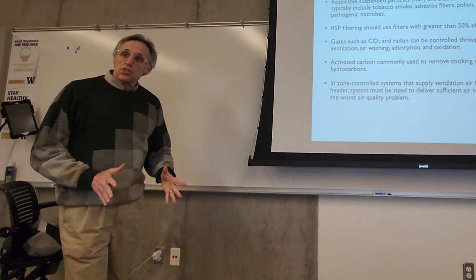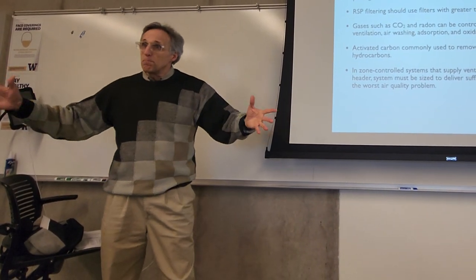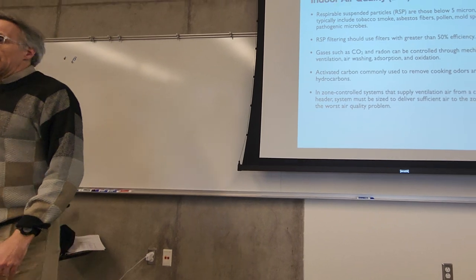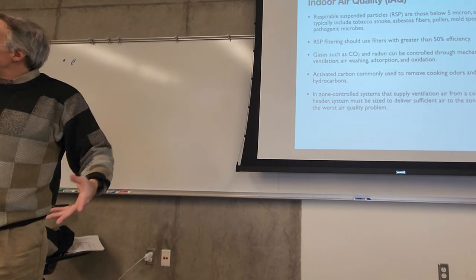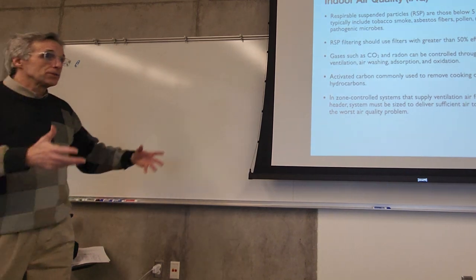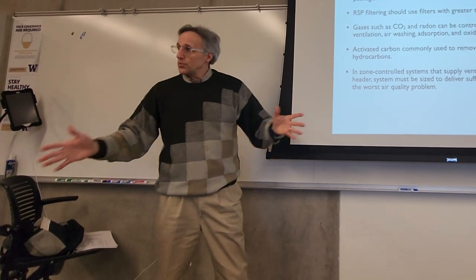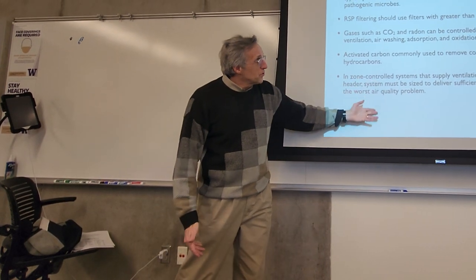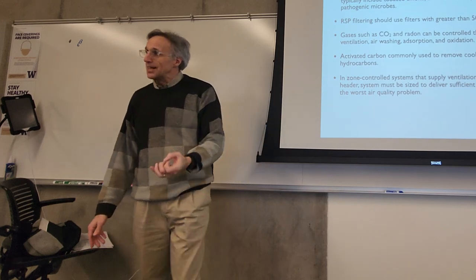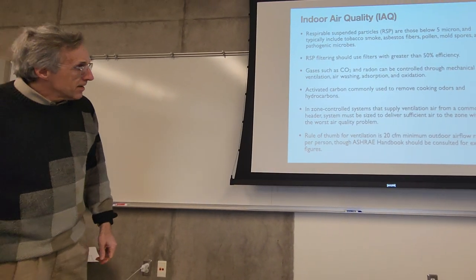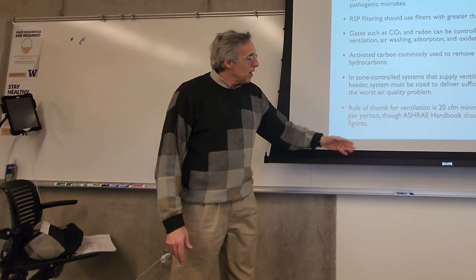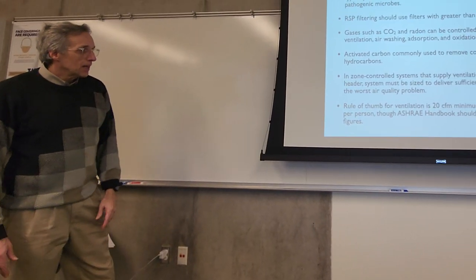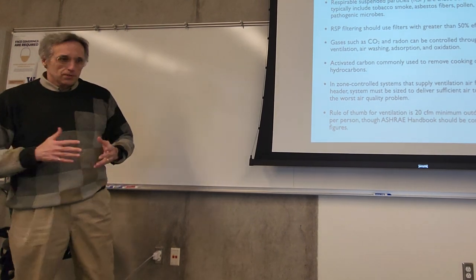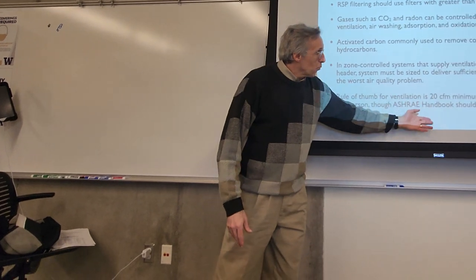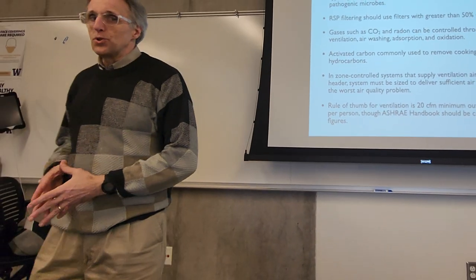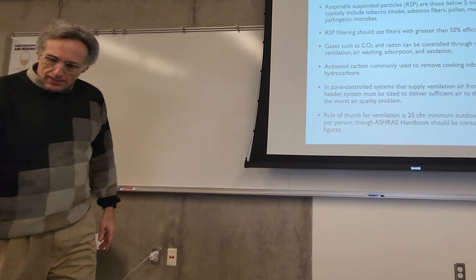Yeah, so then you've got multi-zone systems, where different parts of the building need different amounts of ventilation. Usually you'll have a common header coming in, not always, but usually it's more economical to have a common ventilation header, and then you peel off to different zones. In that situation, the zone that has the worst air quality problems dictates the design. And a rule of thumb is 20 CFM minimum outdoor air per person. And that's just an absolute minimum. There are standards based on the purpose of the space and what people are doing. Yeah, we'll get more into that next time.